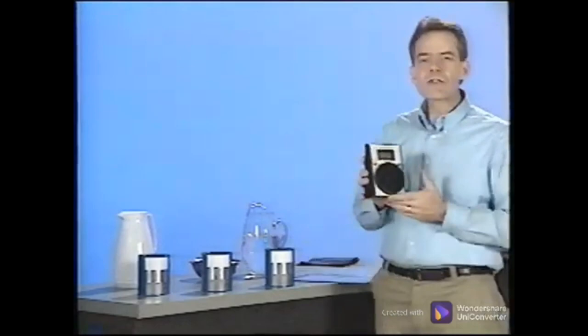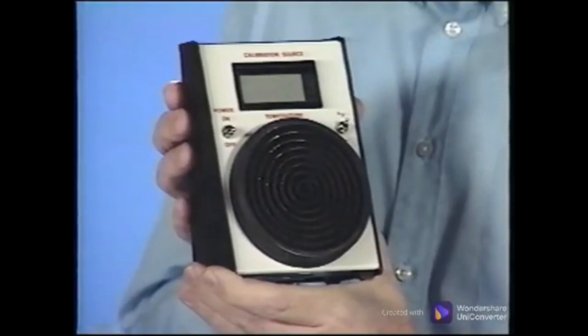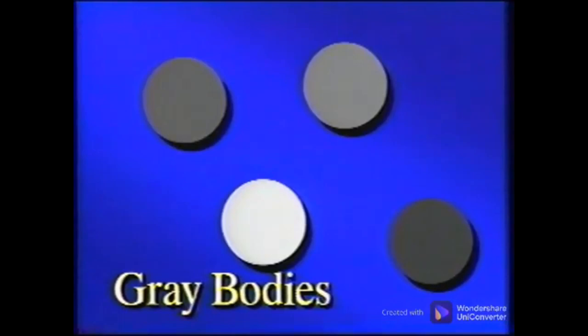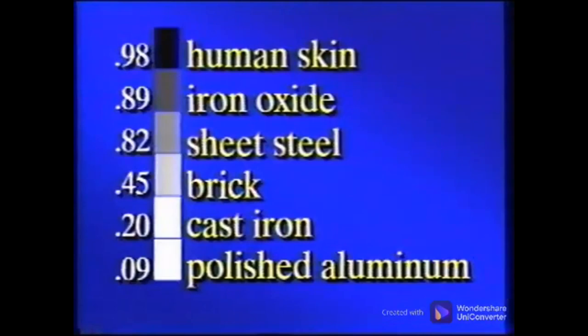All objects are rated on their emissivity. A perfect emitter has a value of 1 and is called a black body. In the real world, there are no perfect emitters or black bodies, but all objects have a fractional value and are called gray bodies. Manufacturers furnish a table of emissivities for various materials.